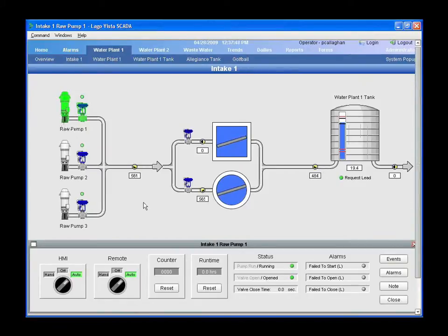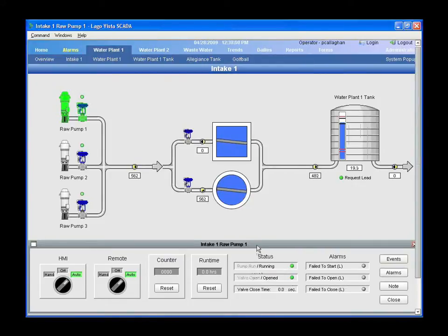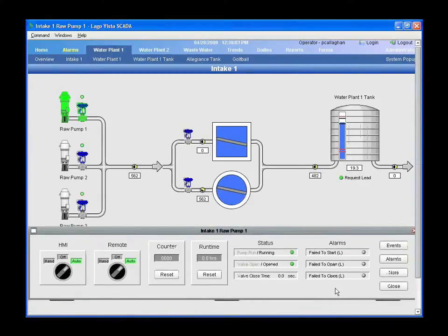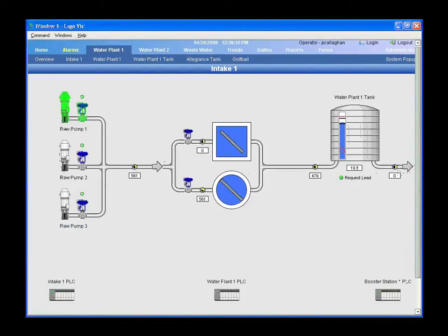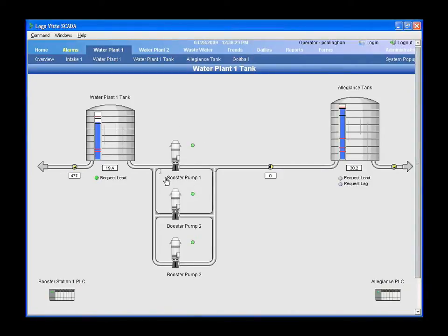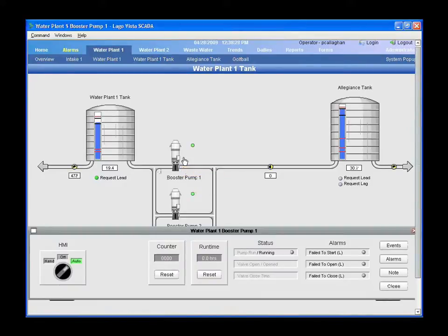This pump here has most of the features — we don't have some of the status here, so I end up graying out those items. The popup window for the pump is one generic window I created; I don't have to create extra windows. I just tell the system that a particular tag isn't used by this pump. The object I created is standard for all pumps throughout the system, but if we don't have status on a valve, I just tell the system it's not there.